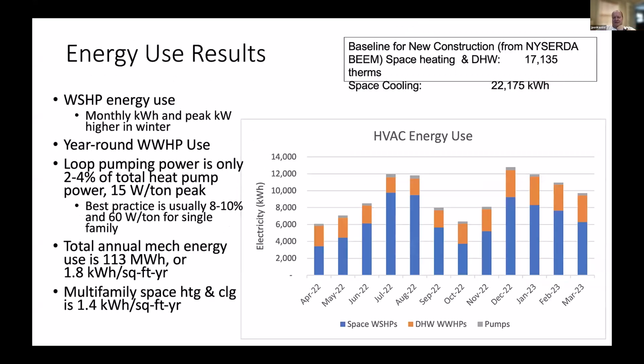So the interesting part here, and this is now looking at the energy flow or the total energy use. So this is the electrical use for the GEO system. And this is the summertime over here. And this is the wintertime. And you can see that the system uses just about as much energy per month in the wintertime as it does in the summertime. Also, the hot water production is slightly less in the summertime compared to the wintertime. And that is probably due to the fact that the cold water coming in is much warmer in the summertime, around 60 degrees max, compared to the wintertime where it drops down to around 45 degrees. Then we have the shoulder season where, of course, the space conditioning is going down. It doesn't go down to zero because some people like it warmer, some people like it colder. But it's significantly less than in the wintertime.